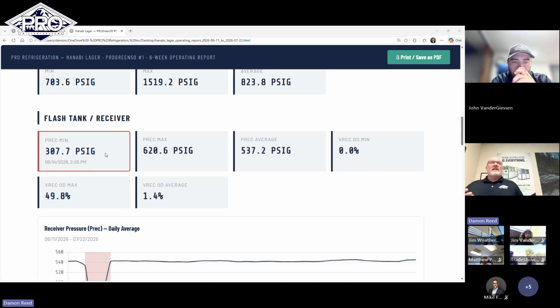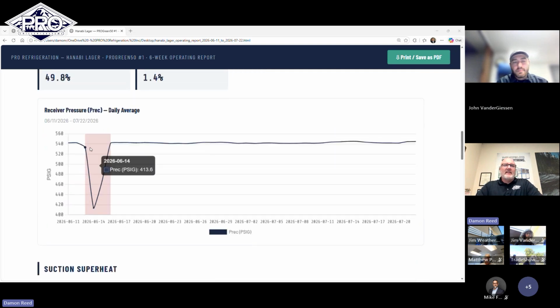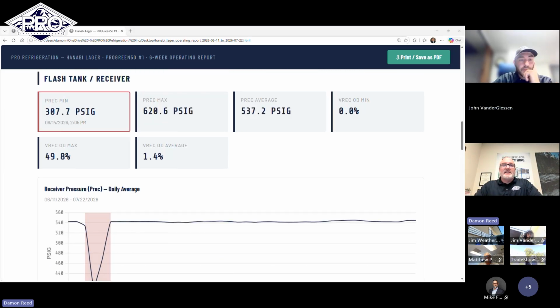So when I see a 300 psi receiver pressure in this report, right away that's a red flag that says, man, that's awfully low. So we went ahead and got a graph of that as well, the same event overlaid with the loss of refrigerant. Seeing low receiver pressure is a red flag to say, hey, we don't have enough refrigerant.